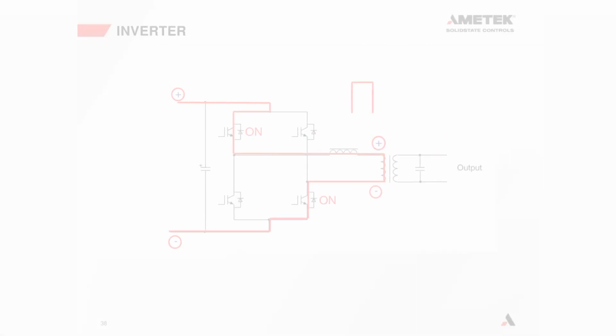An inverter, rather than use SCRs like the rectifier bridge did, uses IGBTs to change that DC into AC. And it's quite simple. What it does is it switches the IGBTs, the transistors, on in a certain way to get AC from DC. So basically, you can see here, we have this IGBT turned on, and it will make this side of the transformer positive. But remember, we do have to have a return path to the negative. So therefore, we also switch on this IGBT, and that makes the negative get to the bottom of the transformer. So obviously, they are both going to be turned on at the same time, and it will give us a square pulse on the input to the primary of the transformer.